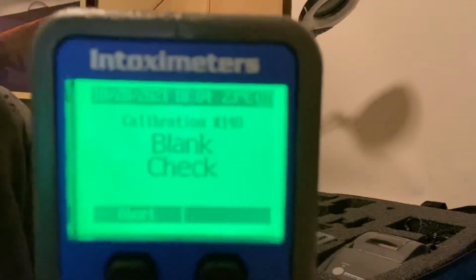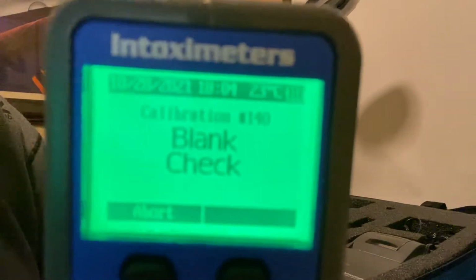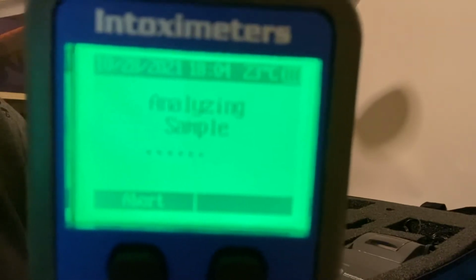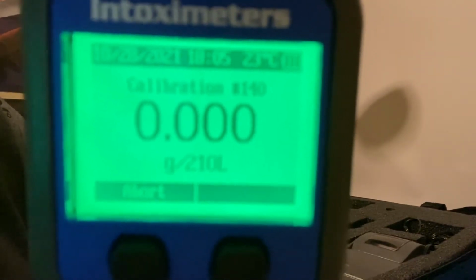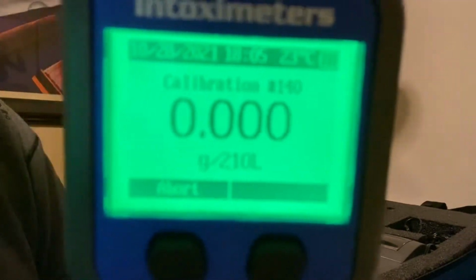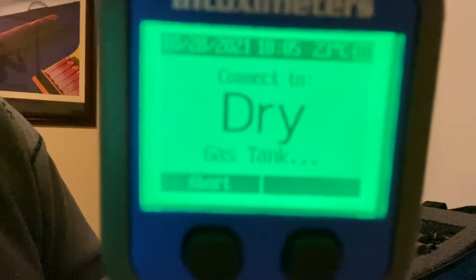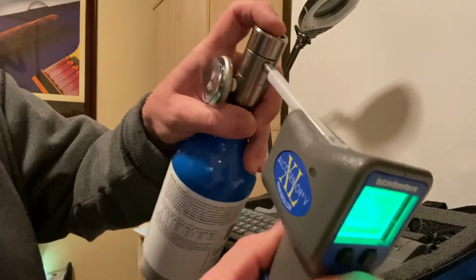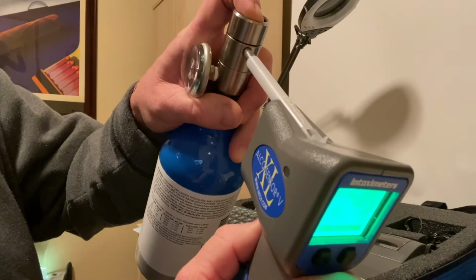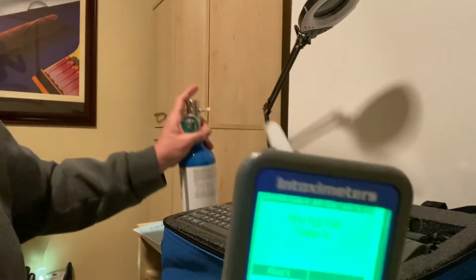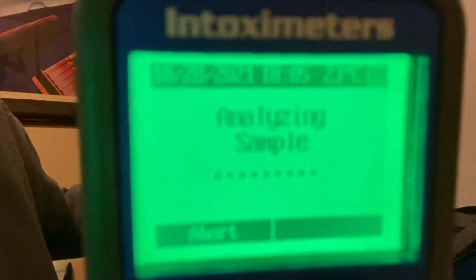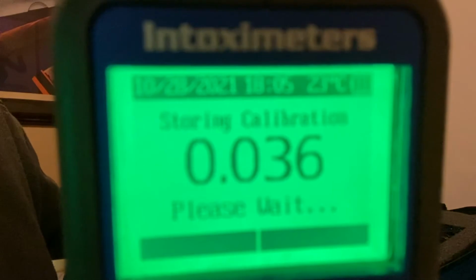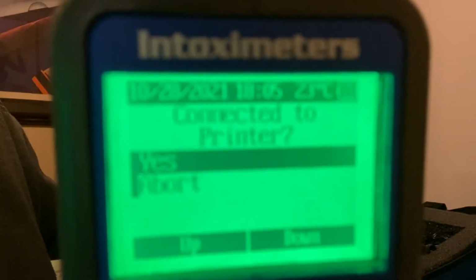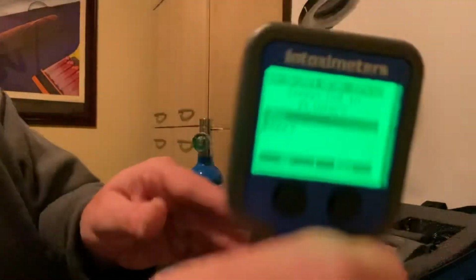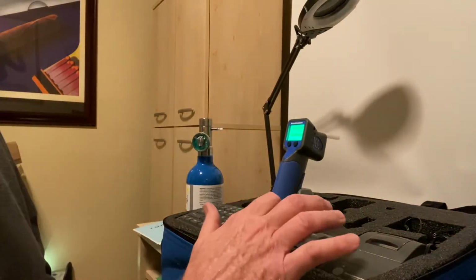And now it's going to do another blank check, air check that's in my room right now. Again, I should get 000. And I did. And then it's going to ask me to submit a sample. And I pull this out, I put it in here. Again, 1, 2, 3, 4, 5, 6, squeeze the trigger. It's analyzing the air sample from the tank, and it's .036, which is on the money. It asks me if I'm connected to the printer, which I am, so I'll put it in the docking station and hit enter.